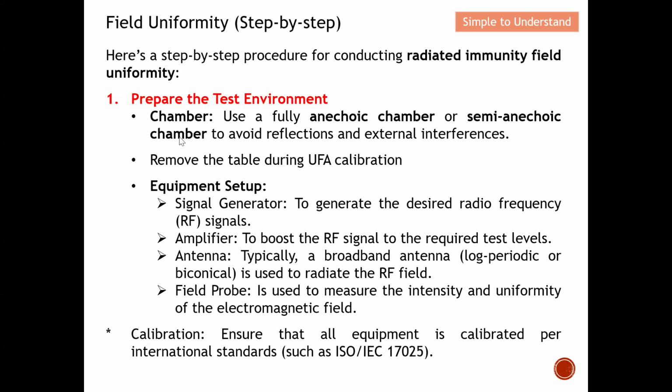Next, when we do this field uniformity, please ensure that you remove the table. When we do the RI, we need the table inside, but when we do this field uniformity, we need to remove the table. So keep this in mind.